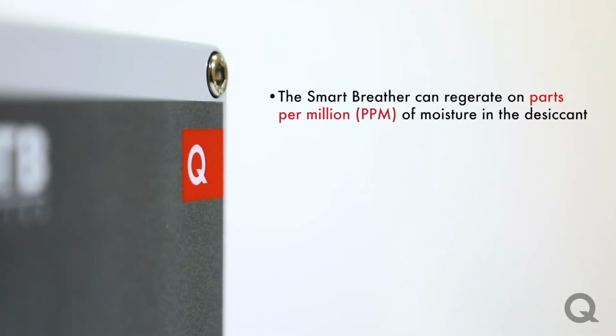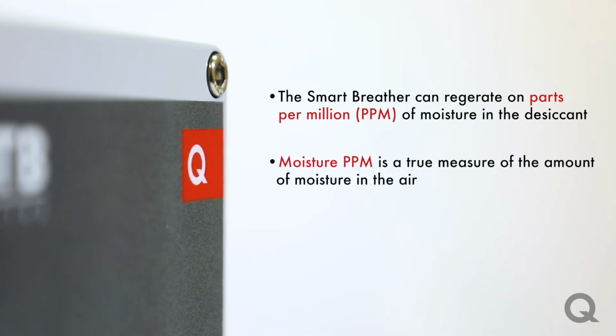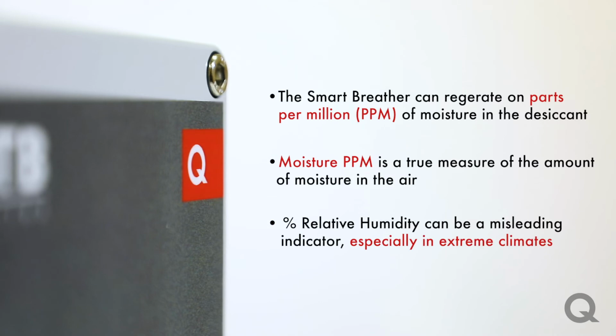A new feature that we added is that the breather can now regenerate on parts per million of moisture in the desiccant. Moisture ppm, parts per million, is a true measure of the amount of moisture in the air, or in our case in the desiccant. As temperature changes, percent relative humidity can be a misleading indicator of true moisture level, especially in extreme climates.